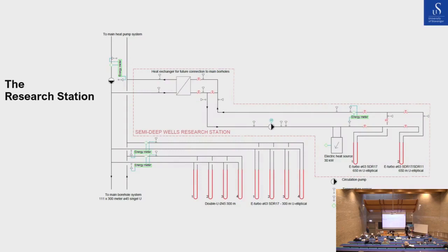Here you see our research station, which is going to be built within the plant. As I said, the standard types are just there, connected to the main system, but we have equipped them with energy meters. We're always measuring the flow rate and the temperatures and comparing them with what goes on in the rest of the system. And then for the semi-deep boreholes, the plan is to build a sort of permanent thermal response test system where we reject heat and measure the temperature response and use that to determine the ground conditions.